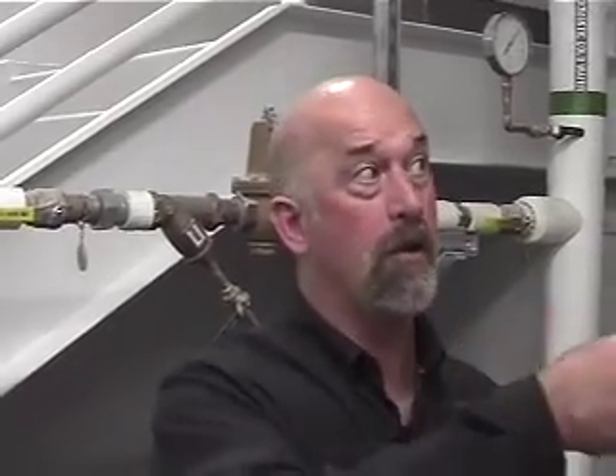On the shell and tube heat exchangers, what can go wrong? Again, water hammer is the main culprit, and corrosion. So you want to make sure that you inspect these tubes periodically for scaling, which we call fouling. Once they start fouling up, the hole in that tube becomes thinner, and you don't get the same heat that you were getting when they were brand new. That's why we put a fouling factor on when we size them, and it's pretty small. So when they start fouling up and getting corroded, you want to change the bundles out. Also, if we have water in this line right here, again, the steam line, the steam is in the shell and water is in the tube, right?